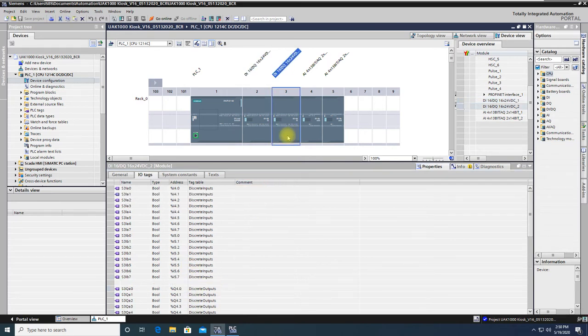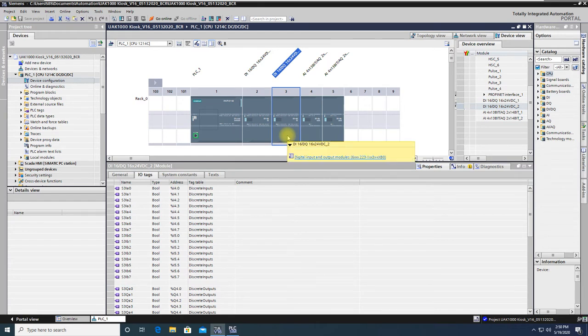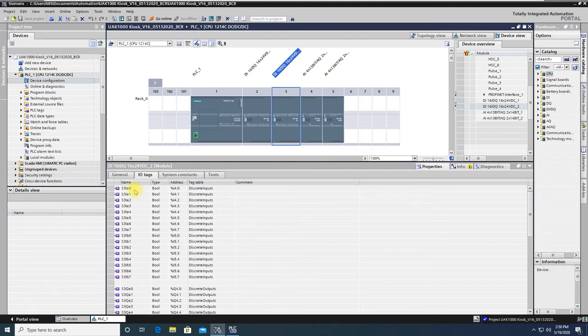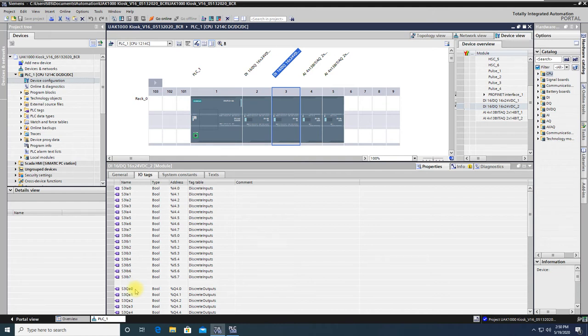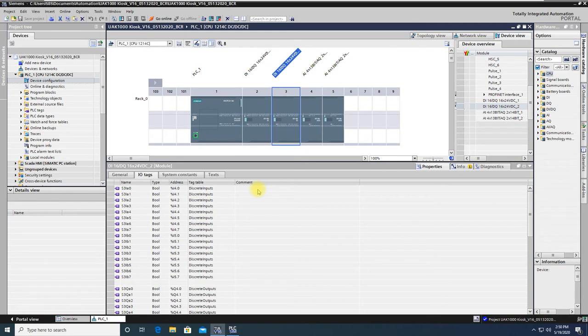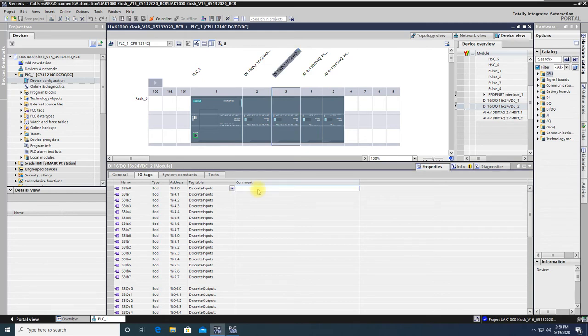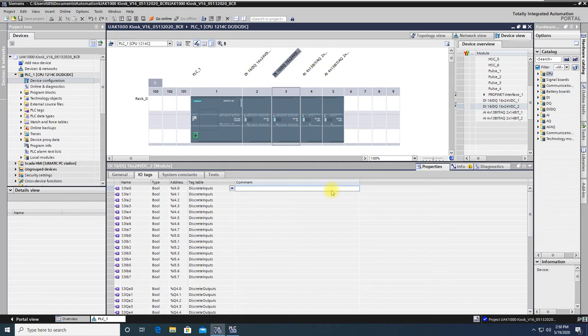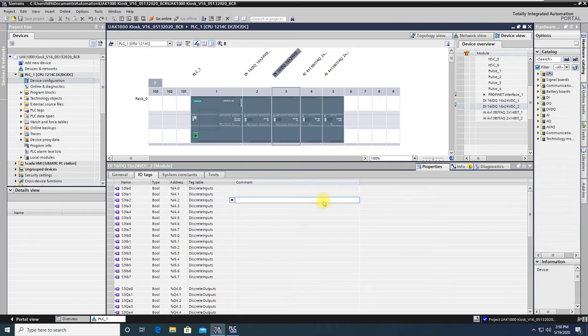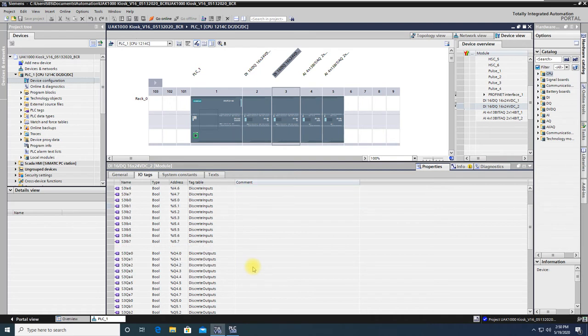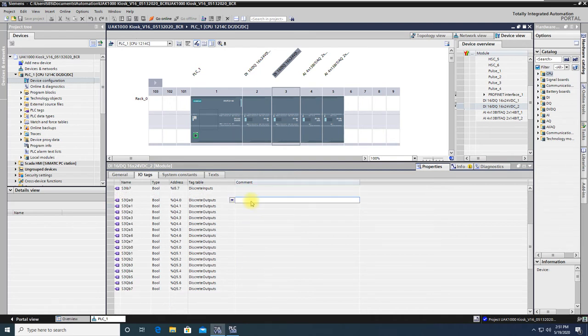Slot 3, same idea. However, although the internal addressing changes, we use the tag name that tells you exactly where the wire is going for any particular input in slot 3, or any particular output in slot 3. So this, we hope, will be the way that you'll be able to troubleshoot our system faster, just by looking at the wire addressing that we've done on the terminal blocks that are in our system. We want you to incorporate the comment area to tell us where you'd like to wire it on your system. So comments are a wide, verbal area that you can use to describe what you're wiring. Maybe start push buttons, stop push buttons, high-level limit switches, low-level limit switches, whatever you choose to wire as a discrete input. And the same idea on the discrete outputs. So here is another 16 discrete outputs that could be used in our system.